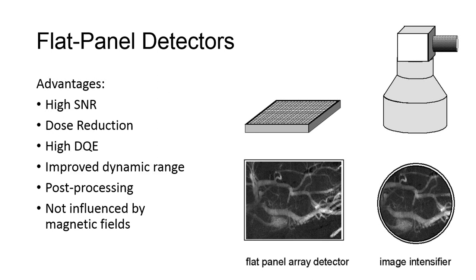Flat panel detectors also have much higher signal-to-noise ratio than image intensifiers. A post-processing technique called temporal frame averaging allows for a reduction of noise by as much as 44%. This process averages each pixel value for one or two frames prior to, and one or two frames following, a specific captured frame. Other advantages for digital flat panel detectors are contrast enhancement capabilities, high DQE (detector quantum efficiency), and improved dynamic range of the detectors.